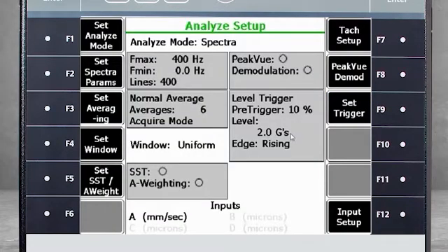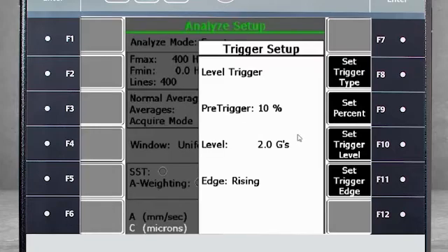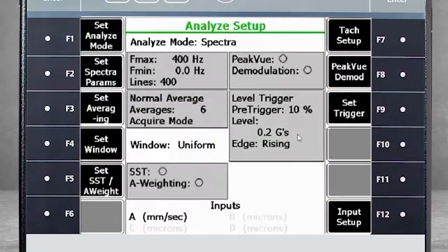The second exception to the default settings is just the opposite. The machine may have a very rigid structure and require significantly more force to impact the machine to 2.0 Gs. In this case, you may want to lower the trigger level using the same steps, but perhaps use 0.2 Gs as the trigger level. Other than these two exceptions, the default template should handle most of your applications.